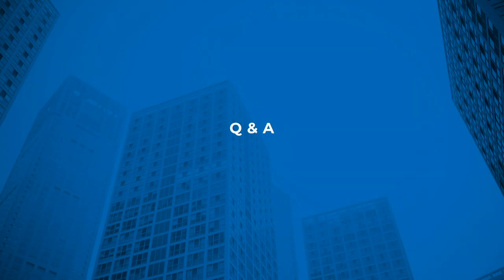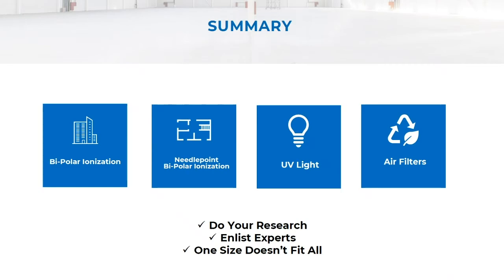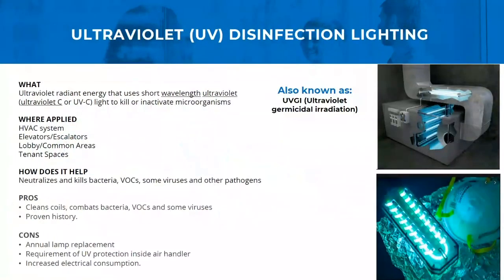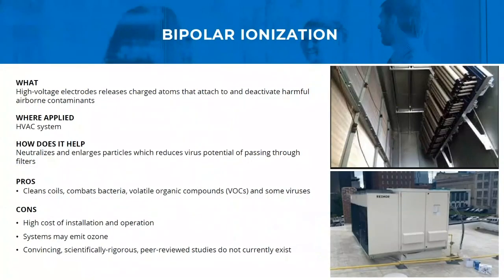Okay, next question. Where is the best location to install needlepoint systems? We are looking at installing between filters and coils. Would this be the correct location? That is correct. You can place a needlepoint system really anywhere in the ductwork, but as mentioned, the best place to install a needlepoint system would be between the filter and the coil. It would then clean not only the coil, but the filters as well. And as mentioned, it also makes the particles larger so that they get caught in the filter. So that's the absolute best place to install a needlepoint system.